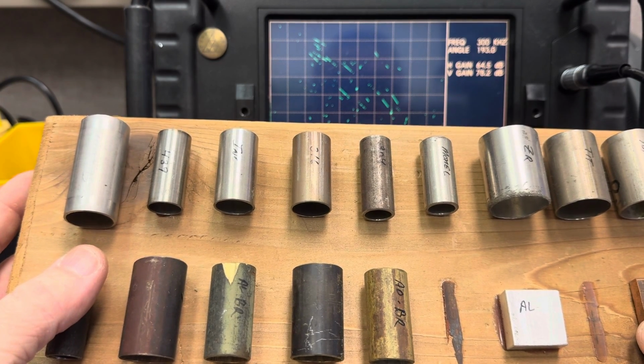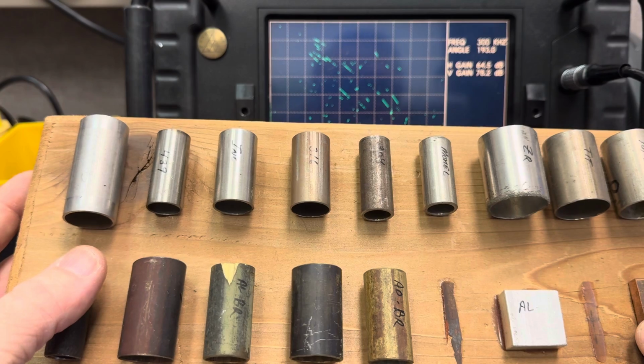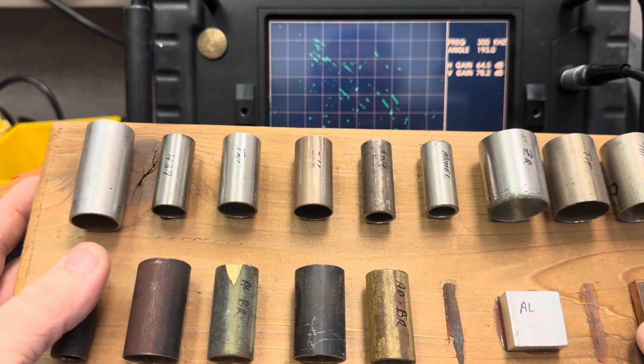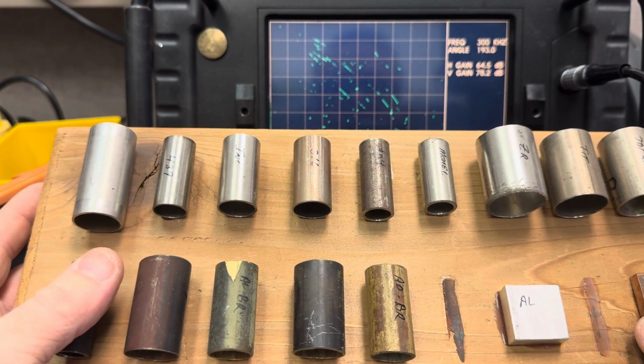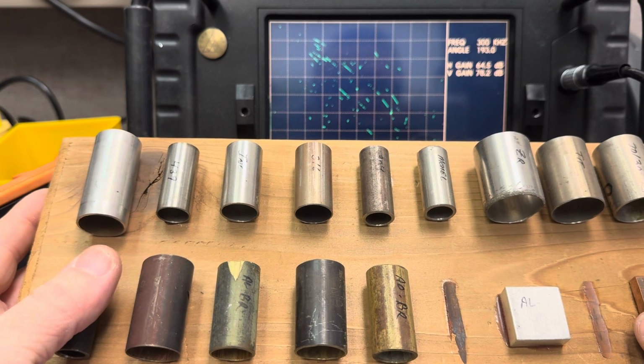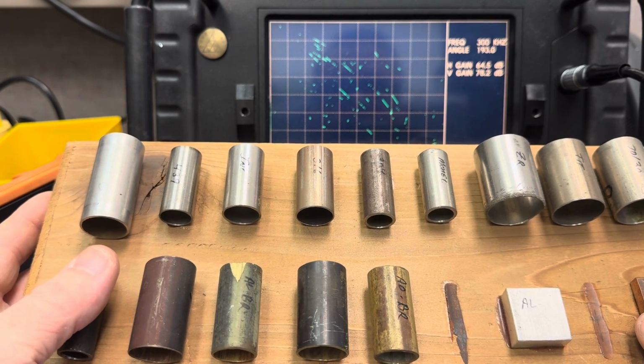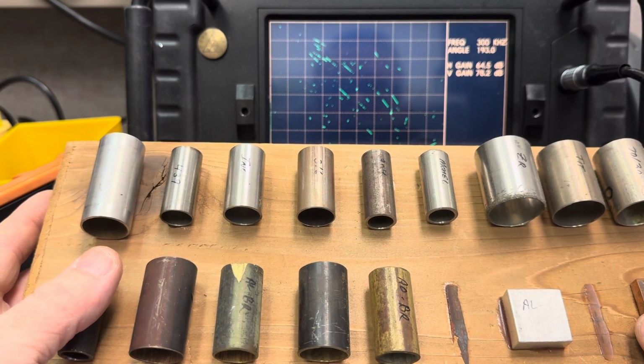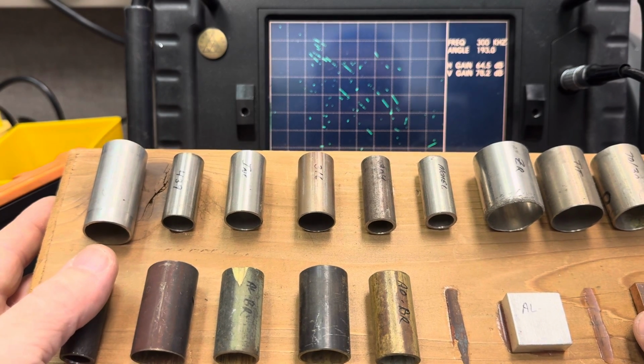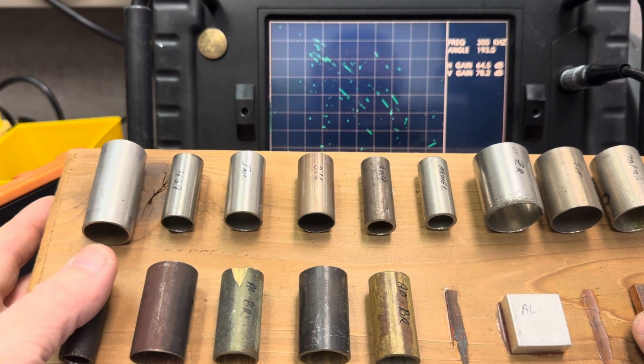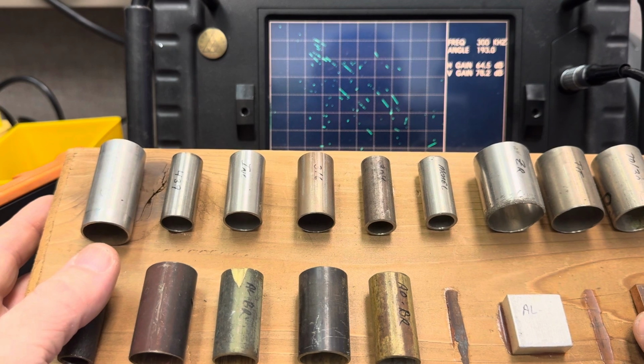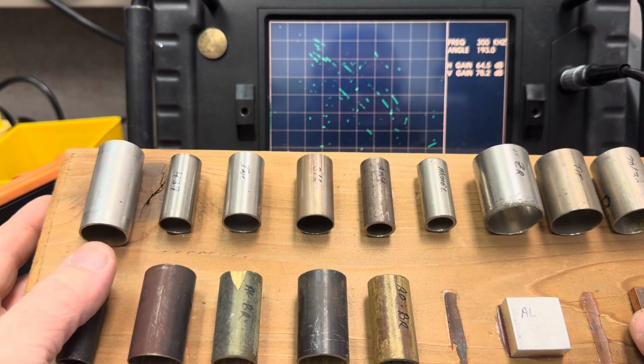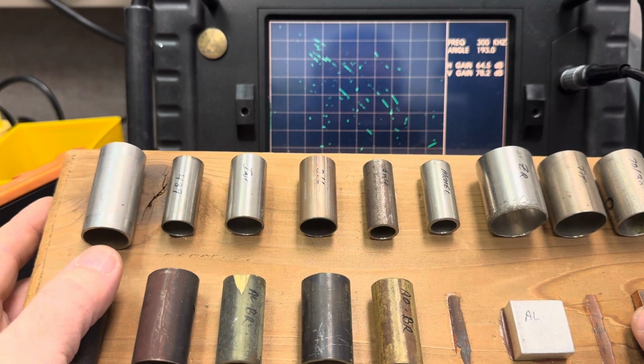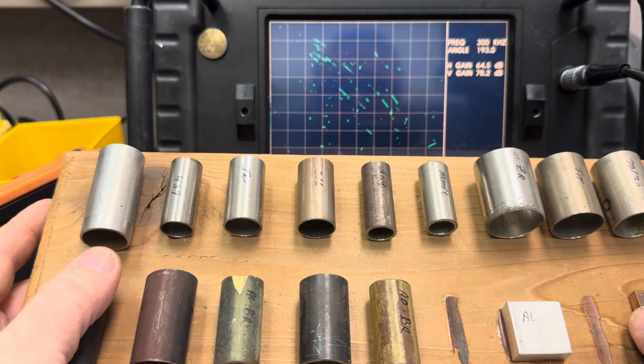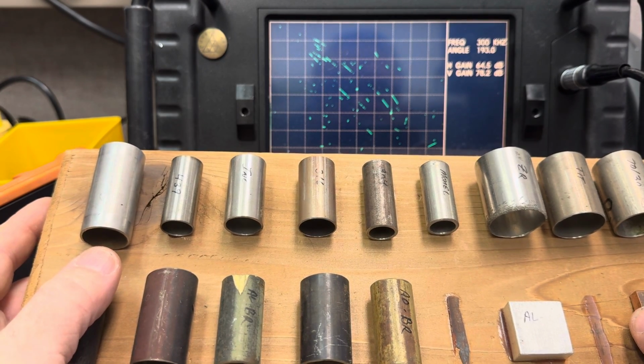So when you hand the client a report and you find an indication, you're going to reference it from a tube support plate. The lazy way to do it is just call it from the tube end, but tube end plus 385 inches, that's not ideal. But if you could say tube support plate number 5 plus 1.4 inches, that's a little more specific. And of course, all of the modern data analysis software for large scale tubing inspections automatically landmarks and locates, as long as you input the variables from the drawing. So the actual distances, the bend radius of your tubes.